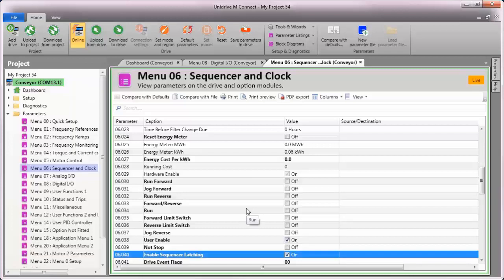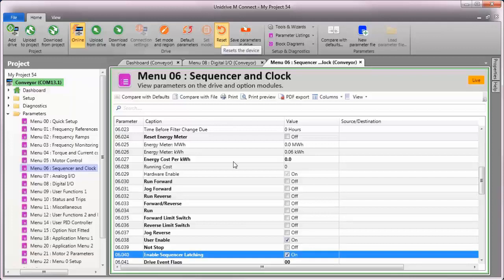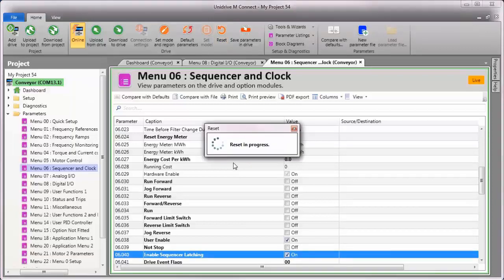The last and most important thing I'll need to do is to perform a drive reset. Anytime you change either a sequencer parameter in menu 6 or a digital I.O. parameter in menu 8, you need to perform a reset on the drive or the changes won't take effect. I'll use the reset button in the control ribbon in mConnect software to do that.